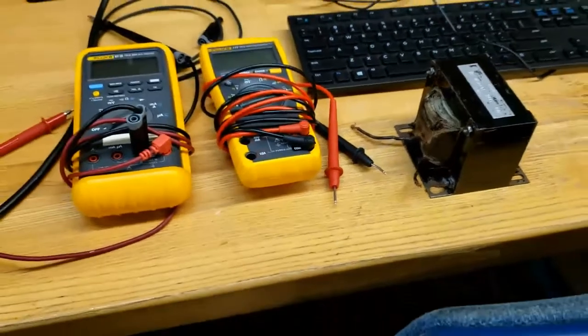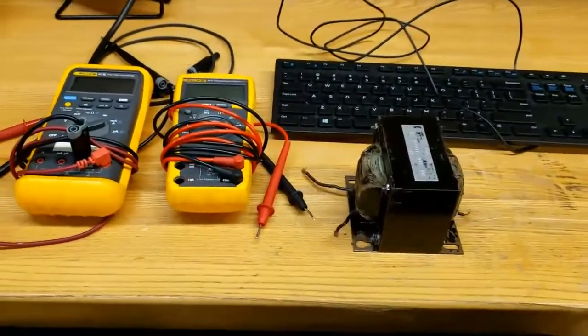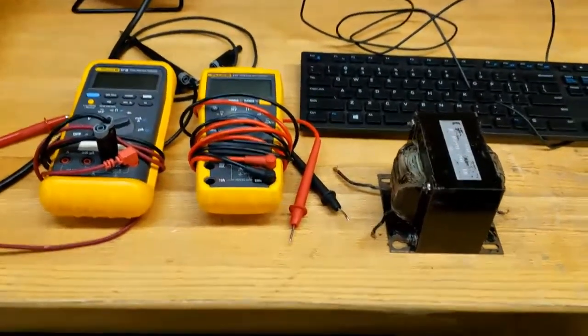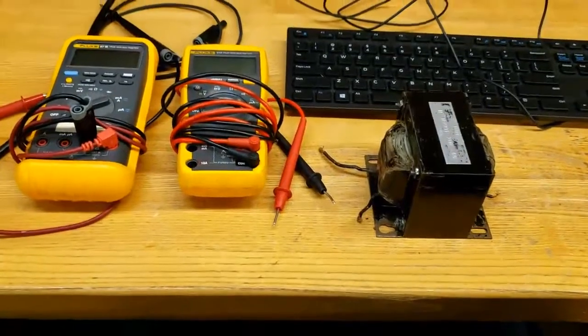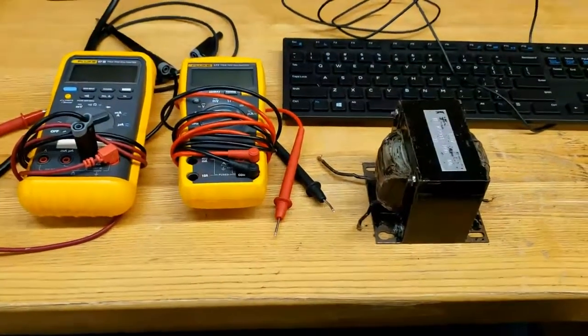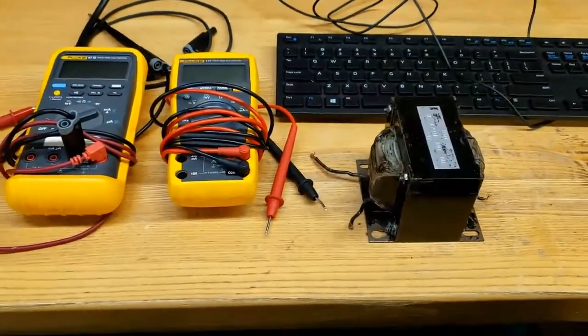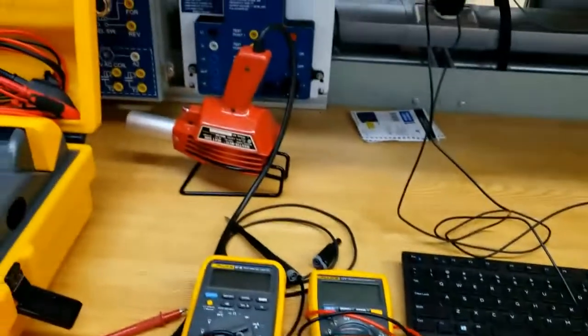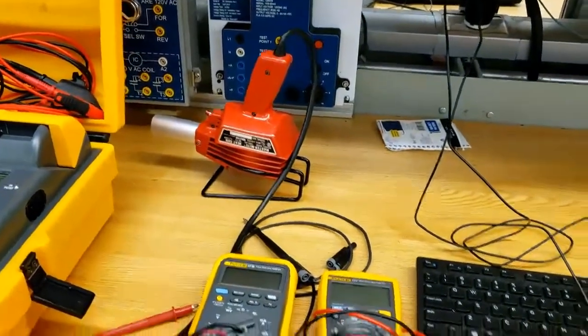You're going to do a 10-minute test. Leave the voltage at that level for 10 minutes. Record the current every 60 seconds, every minute. So you'll get 10 readings. And you can be drying it gently during this time.